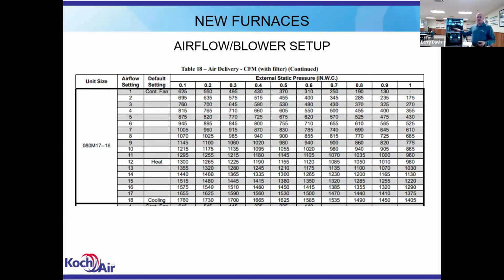And the heat speed is going to be set at the mid range of what they've tested that furnace to get its temperature rise. Your constant fan speed is always going to be set at 1. It's always going to be the lowest setting. So the way we set our fan speed for cooling is we use the chart that you see, and you have your static pressure ranges. So you'll calculate or determine what your total static pressure across the furnace is, and you'll use that scale.